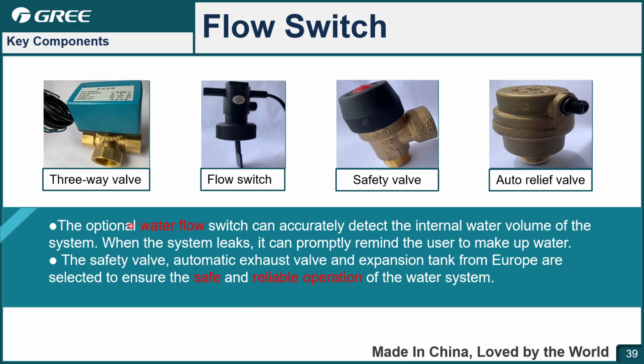Next one, flow switch. For some types, such as the split type and all-in-one type, the 3-way valve is built in to control the water flow direction, and the flow switch detects the water volume and speed to make sure there is sufficient water inside. If there is insufficient water, the unit will trigger the protection to shut down to protect it. Safety valve: if the water pressure is too high, this valve will open to release the pressure to keep it safe. Next one, the water relief valve for air discharge, to discharge the air inside and make sure the water pressure is stable. Okay.